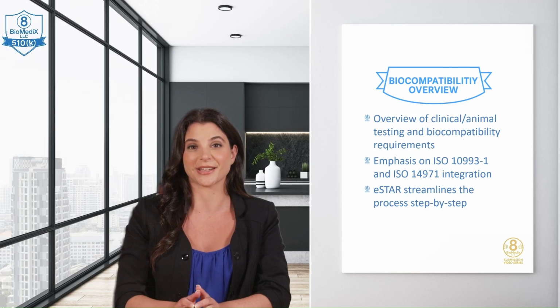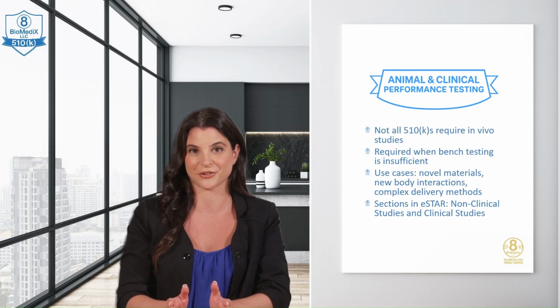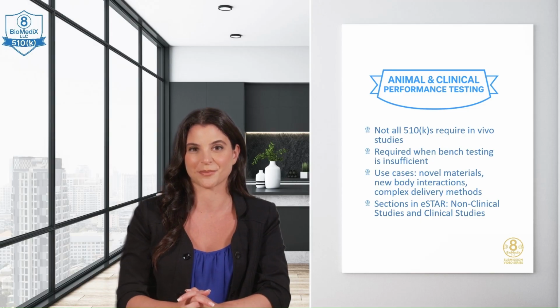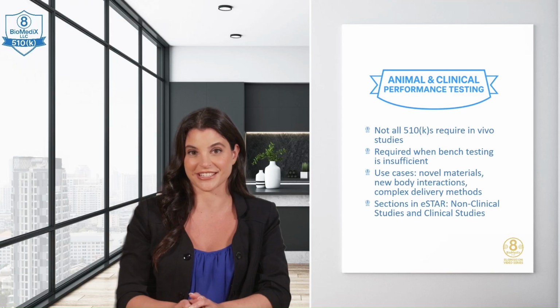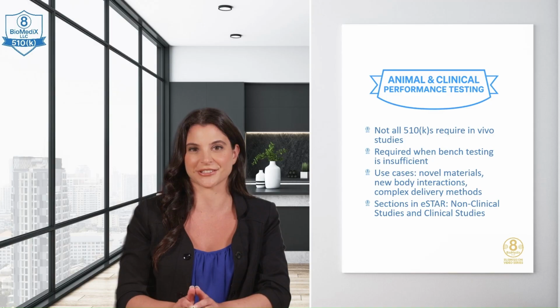Let's dive in. Clinical and animal performance testing. Not every 510K requires clinical or animal studies. These in vivo studies become essential when bench testing alone can't fully demonstrate safety or effectiveness. For instance, if your device uses a novel material, interacts with the body in a new way, or has a complex delivery method, the FDA may expect in vivo evidence. Within eSTAR, you'll find dedicated non-clinical studies and clinical studies sections. This is where you'll summarize and upload your test data.